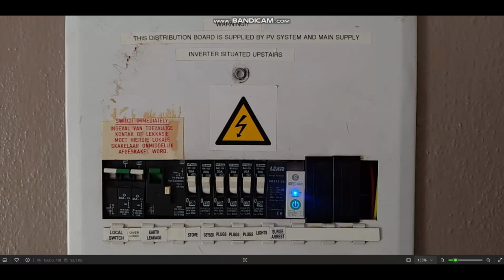What this little gizmo does is it will monitor the voltage, and as soon as that voltage exceeds a certain number, sometimes it's 270, 280, 400 volts, depends on the hardware itself, it will close the circuit and divert that harmful power supply with the voltage spike away from your system.